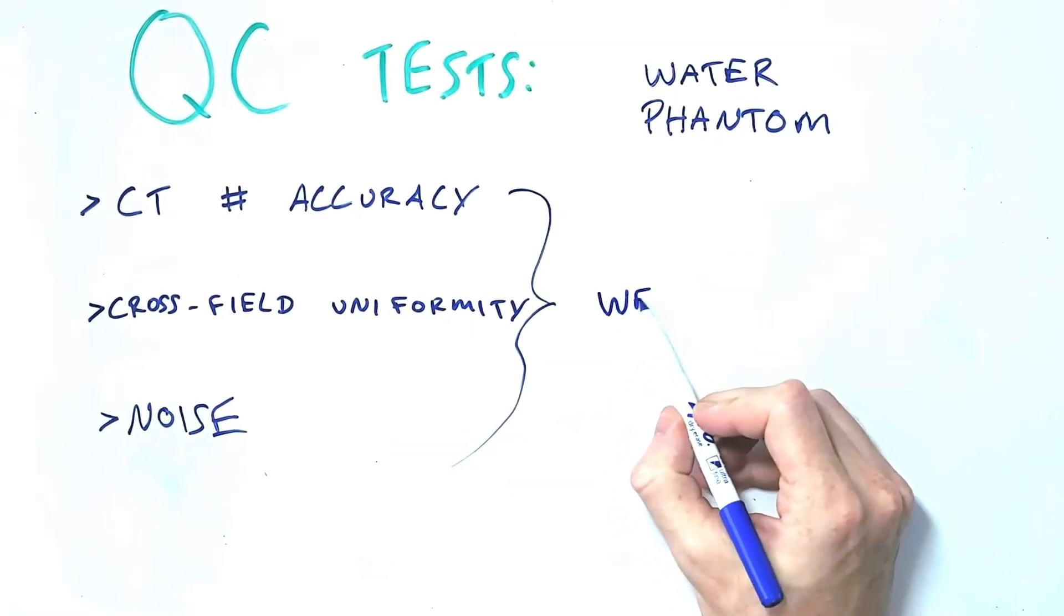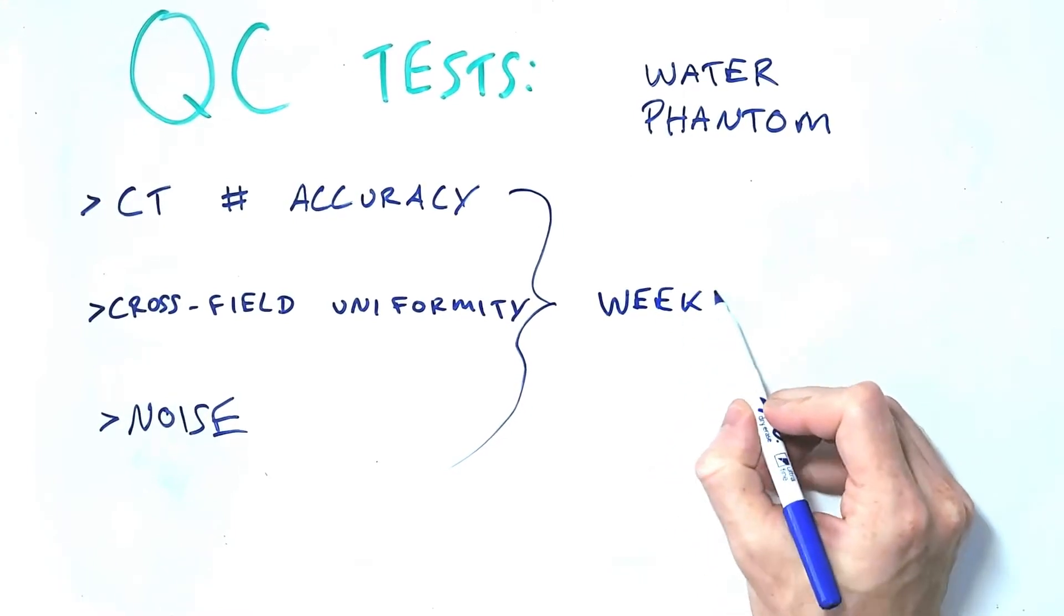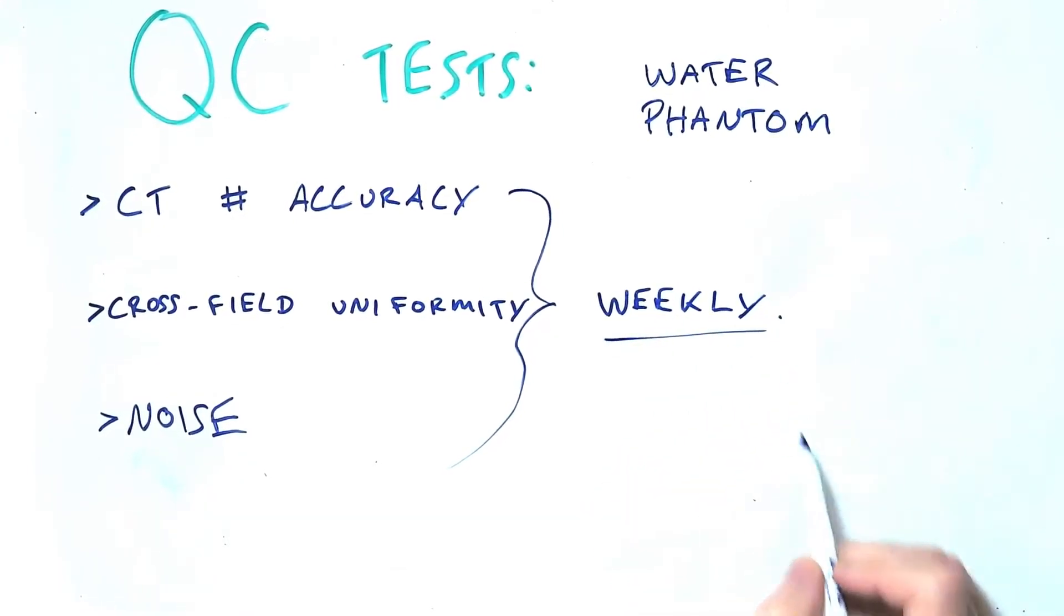These three tests assessing the CT number accuracy, noise and uniformity on a water phantom should be performed weekly.